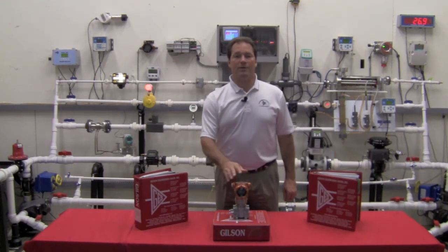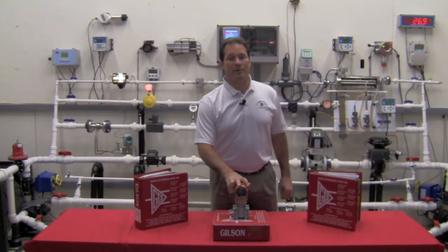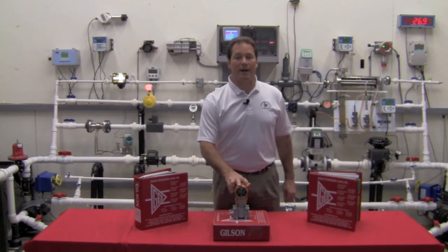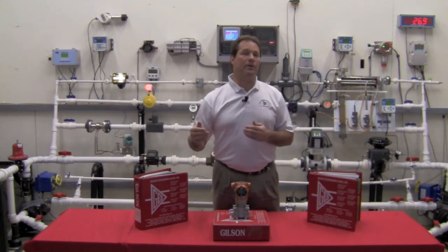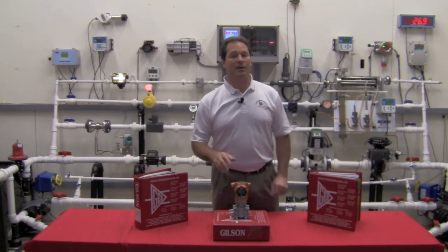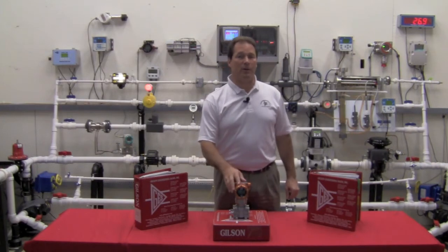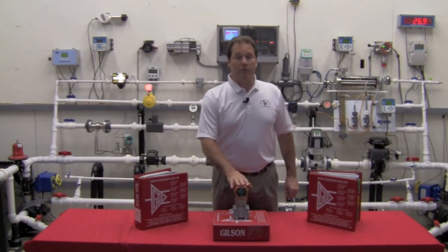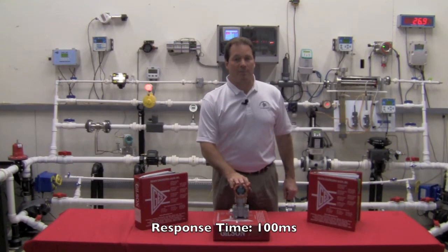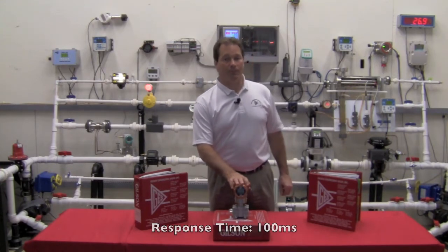What about response time? Standard response on most transmitters is 400 milliseconds. You might have a blip in your process that you wanted to catch that you didn't see if it was less than 400 milliseconds. The standard response on the Yamatake transmitter is 100 milliseconds, 4 times faster than most competitors.